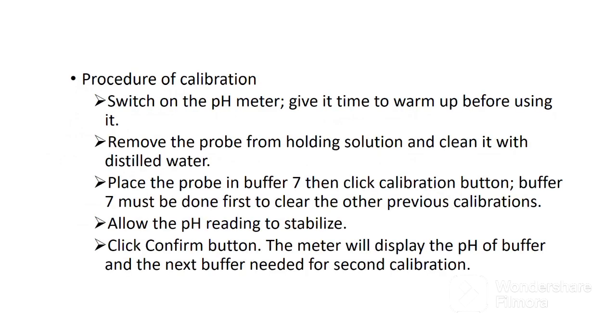Switch on the pH meter, give it time to warm up before you start using it. Remove the probe from the holding solution and clean it with distilled water. Place the probe in buffer 7, then click the calibration button. Buffer 7 must be done first to clear the other previous calibrations. Allow the pH reading to stabilize. When the reading is stable, the confirm tag appears. Click the confirm button. The meter will display the calibrated value and the next buffer value expected.